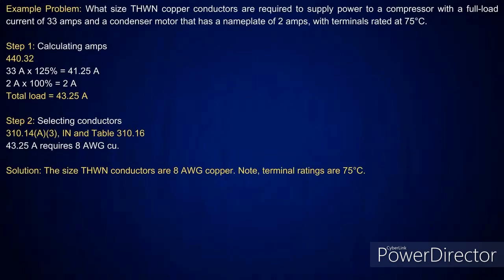Now, this one is where I'm dealing with an AC unit. Here I've got a compressor with a full load current of 33 amps, and then a condenser that has a nameplate of 2 amps. I want to point out that we're saying nameplate. The reason is that when I look at Article 440, you're going to use the nameplate value, and I'm not going to use the motor value given in the tables.